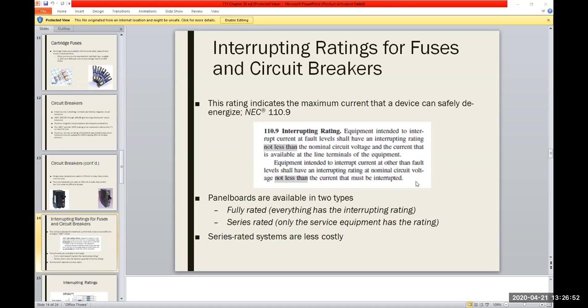See, it's a thing with all this. It's always like lawyer speak, right? Legal speak, if you will. So really, it's like, okay, what the hell does that mean? You basically have to figure, what is my ampacity for this given line, right? And what is my trip point, if you will? You never really want anything to run full bore, at the full maximum. It's got to have a certain settling point, and that's when it'll trip. That's really all it's looking at.